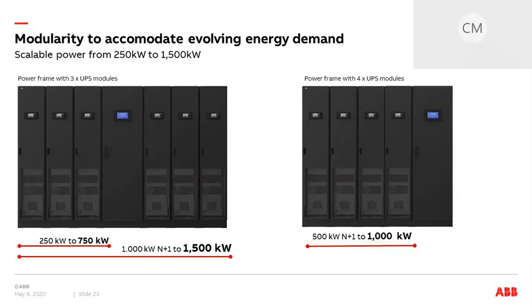For example, the latest UPS MegaFlex DPA consists of power modules with power distribution frames. A power frame can house up to 3 power modules of 250 kilowatts for a total of 750 kilowatts, and there is a power frame with 4 power modules for a total of 1 megawatt. The power frames connected to the power distribution frames can be combined to have UPS solutions from 750 kilowatts to 1.5 megawatts. When operating several cloud infrastructures, standardized power solutions minimize material and inventory, and improve supply chain and logistics.